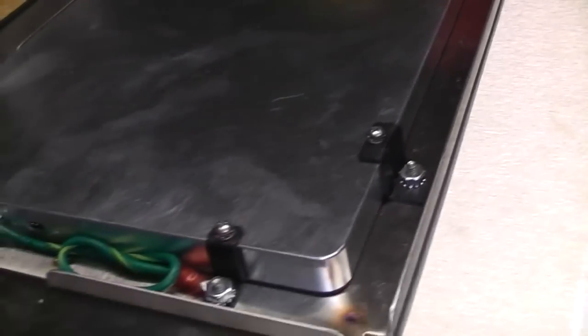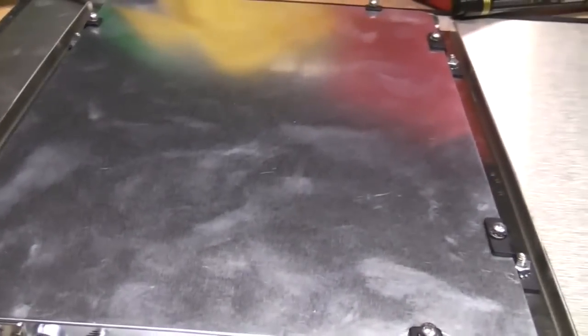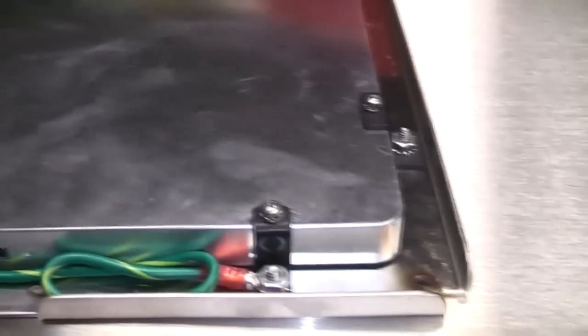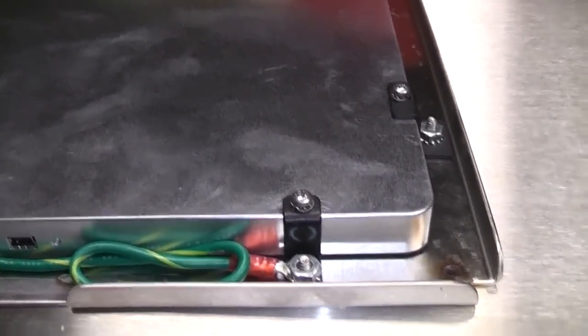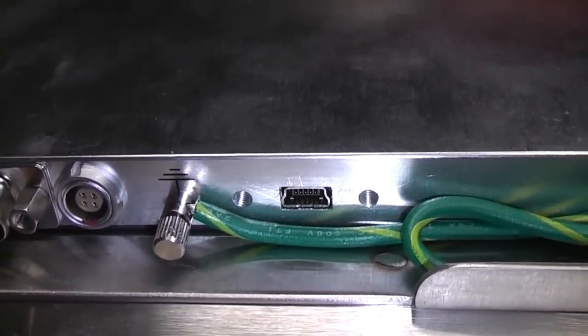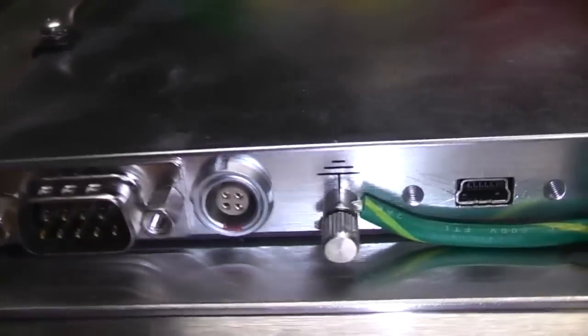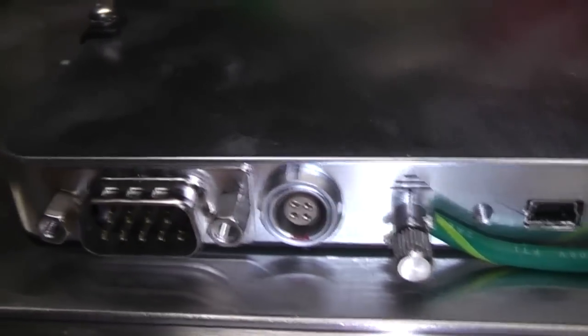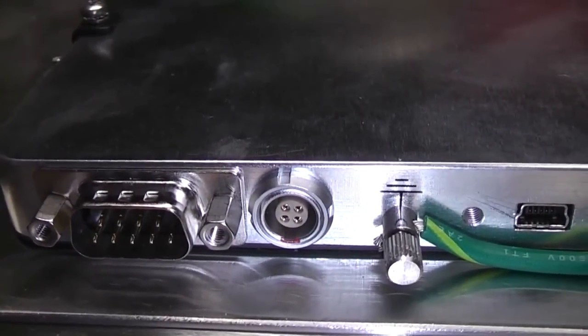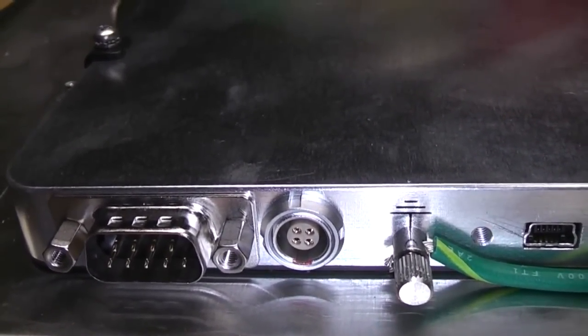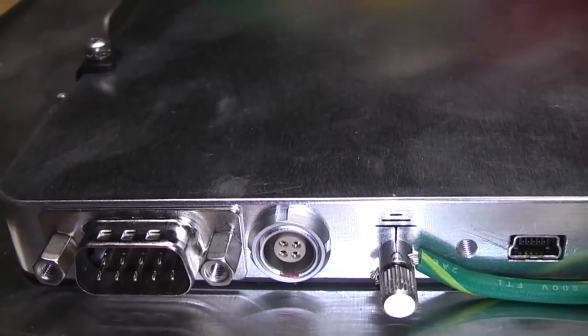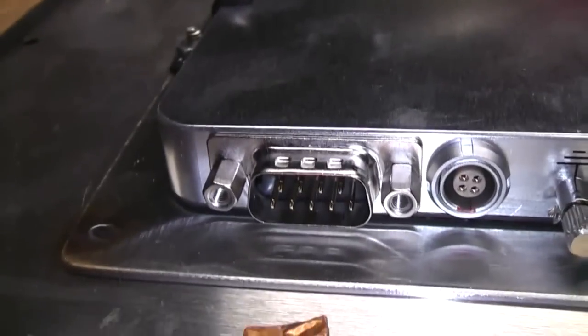Right, so this is the camera module. I think the reason for this shape and size is obviously in some applications this will be replacing an X-ray film cassette, so I'd imagine the form factor is designed to make it easy to replace old film systems with this in the same mechanical form factor. The USB Mini B connector there, the ground connection, and a very expensive Fischer or Lemo connector. I believe that's for external triggering. Because again, if you're using it in conjunction with an old film system, you might need to manually tell it when to take the photo, and that connector is for power.